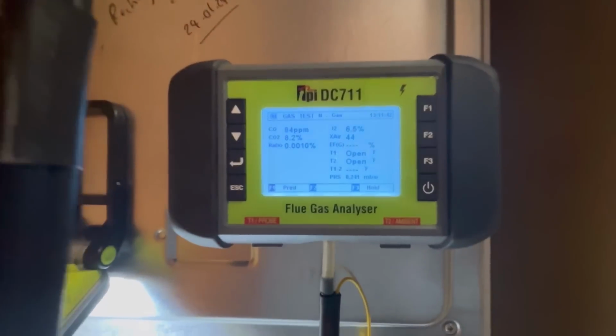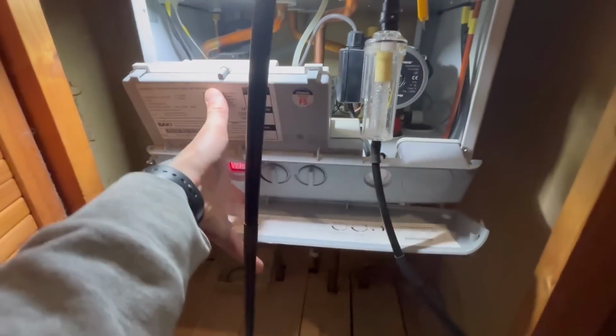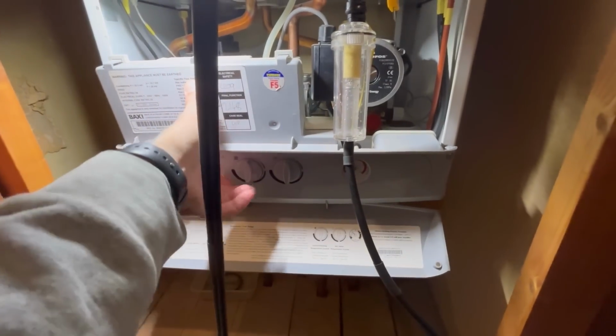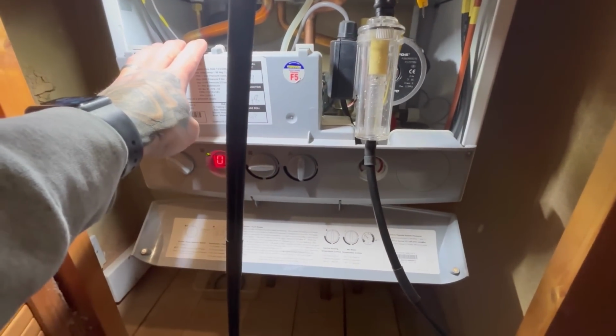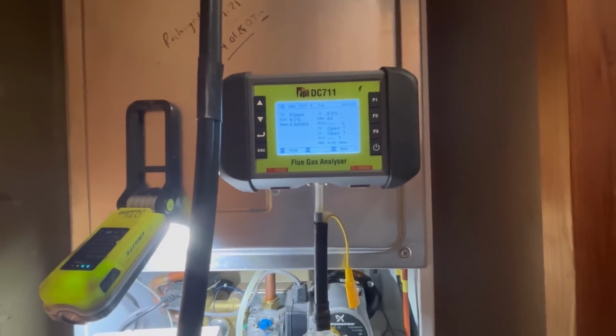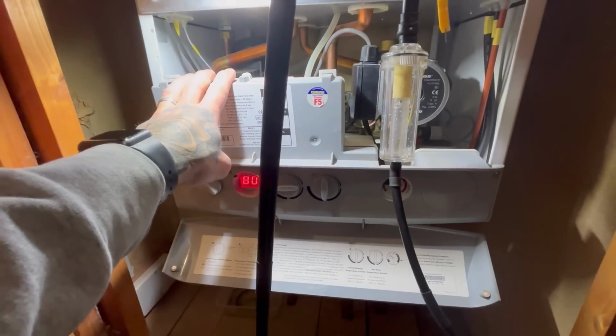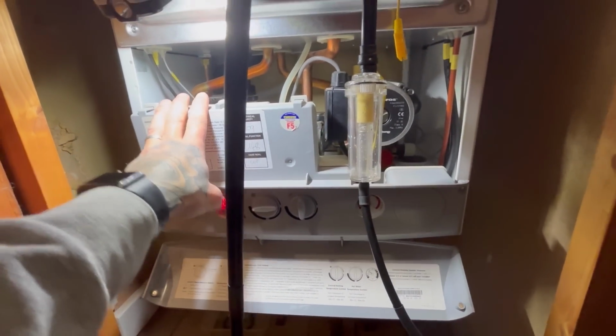I have to whip the heat exchanger door off and see what condition that's in on the inside. Check the trap seal. Common fault on the backseat, flue seal, turret seal. It looks like it's well cemented in. Right, so I've managed to drop it back down. Let's put it in maximum, see if we can get it to make the noise again. Let's check that reading as well now. I've adjusted the minimum. It's locked out. Mint.